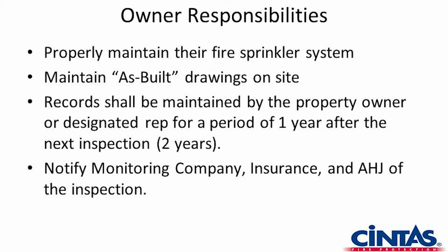Notify monitoring, insurance, and AHJ of the inspection. The International Fire Code is probably the most adopted standard out there. It will reference different NFPA standards depending on what area we're looking at, and it tells us that we will inform the AHJ. As far as the insurance company, that is not something we generally get involved with.